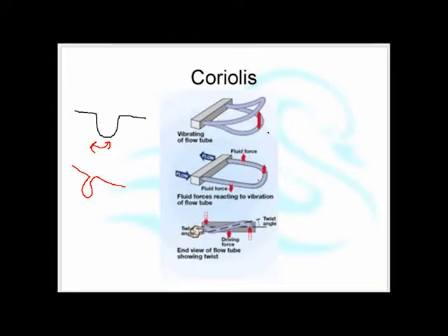No, I got that completely wrong. Let's start that again. I have a bit of fluid. The fluid enters the pipe at this end. The pipe is on an upstroke at the time, so the stuff's happily on an upstroke. A little bit later on, the pipe turns round. The stuff has moved from one bit of pipe to another bit of pipe. So the stuff which wants to go upwards is now being forced to go downwards by the pipe. So the stuff says, no, I'm not going to go downwards, I'm going to carry on going upwards. So what it does is it pulls the pipe out of shape, and that is the twisting that we see.